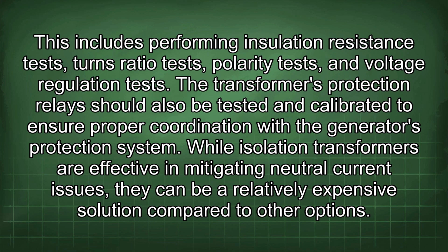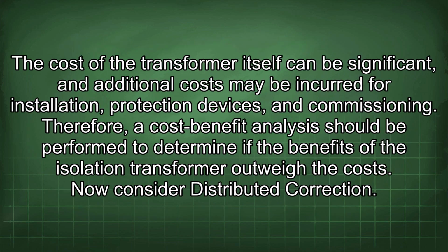While isolation transformers are effective in mitigating neutral current issues, they can be a relatively expensive solution compared to other options. The cost of the transformer itself can be significant, and additional costs may be incurred for installation, protection devices, and commissioning. Therefore, a cost-benefit analysis should be performed to determine if the benefits of the isolation transformer outweigh the costs. Now consider distributed correction.